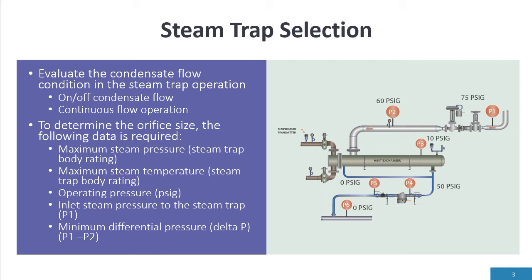We need to know the inlet to the steam trap and the minimum differential pressure. In part one we talked about how to come up with the pressure drop across the control valve, the pressure drop through the heat transfer, so we come up with P4 and P5, which is outlined in this presentation.